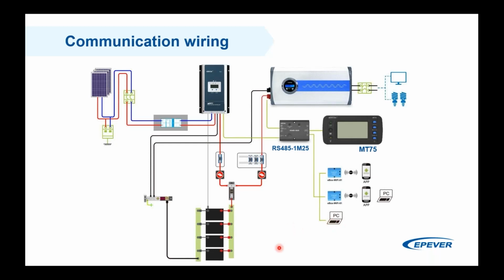let's say software. Or if you have, for example, the Modbus tables, you can even use software like Modbus Pal to map the registers and read the registers that contain the desired data, and then you can easily forward it to an SMTP server or FTP server, or you can even use the EPEVER cloud monitoring system to collect all the data together online, using our IoT module.